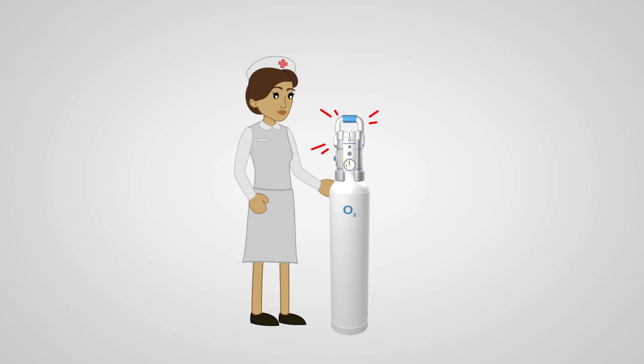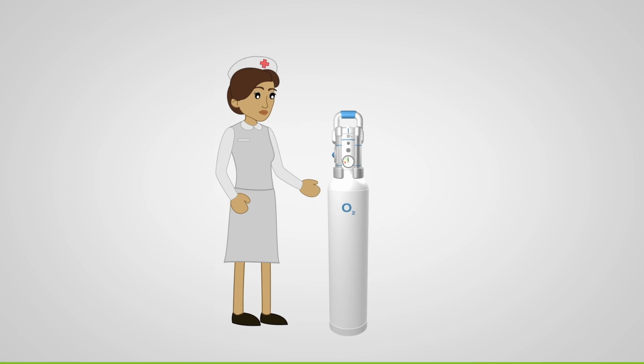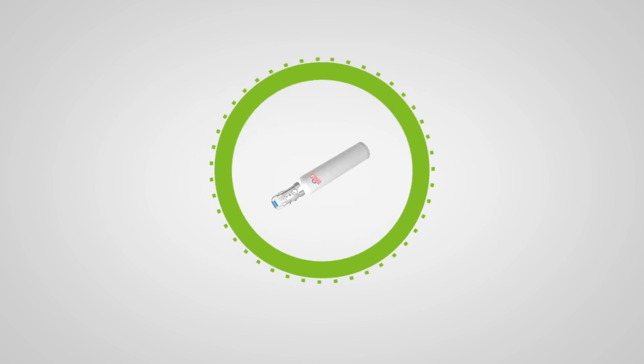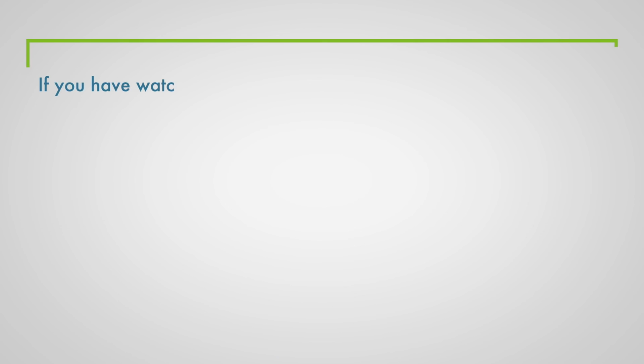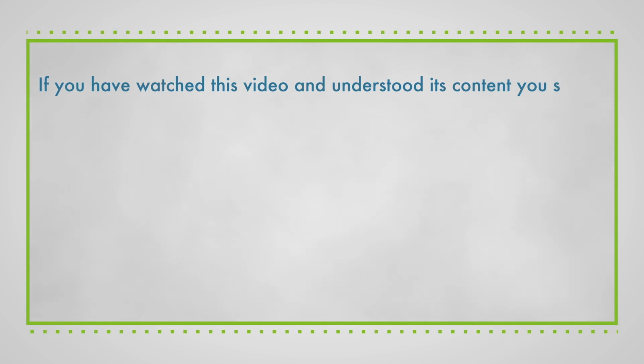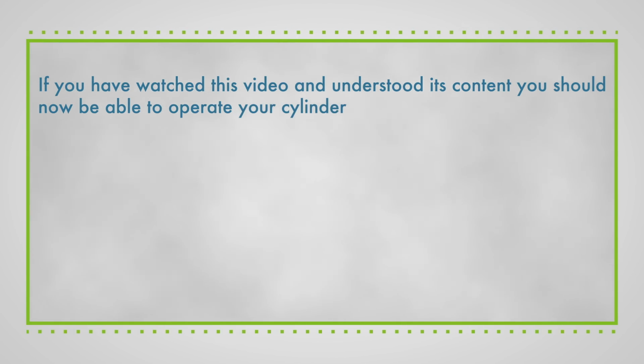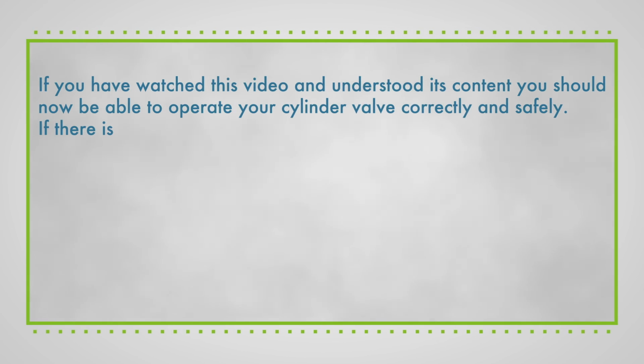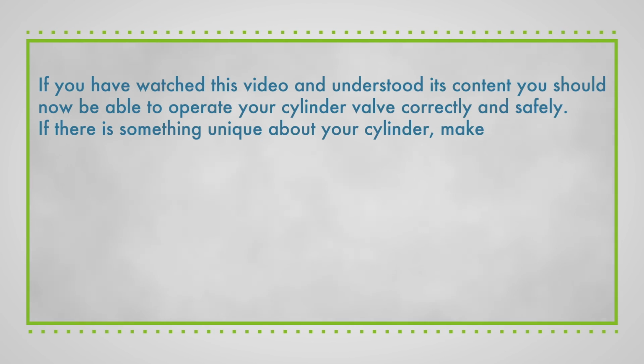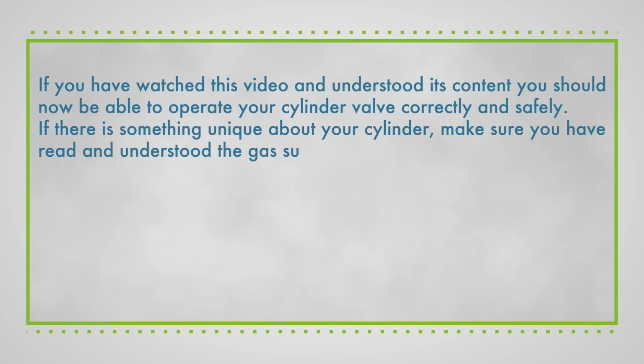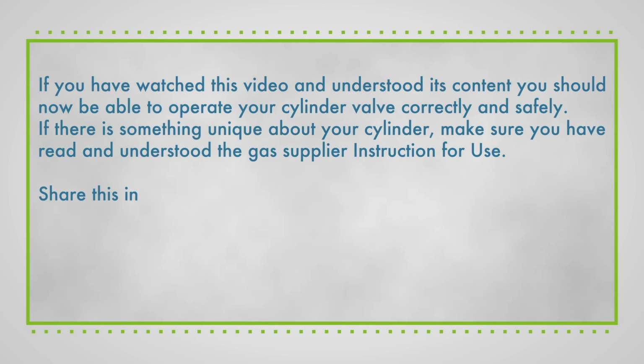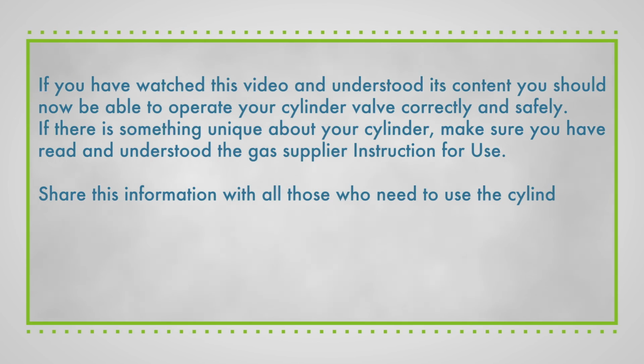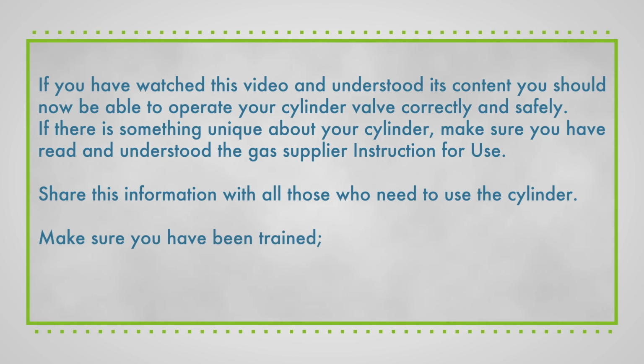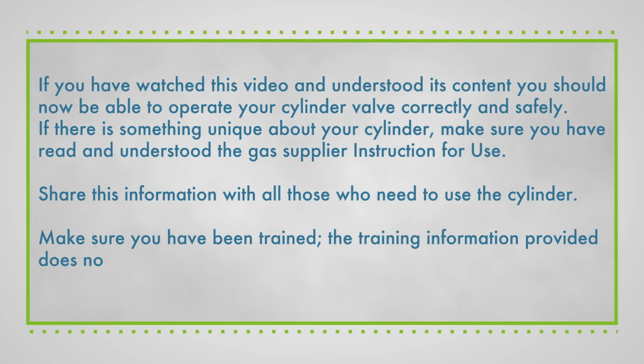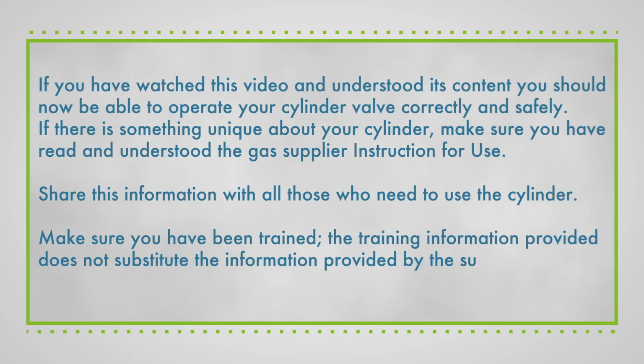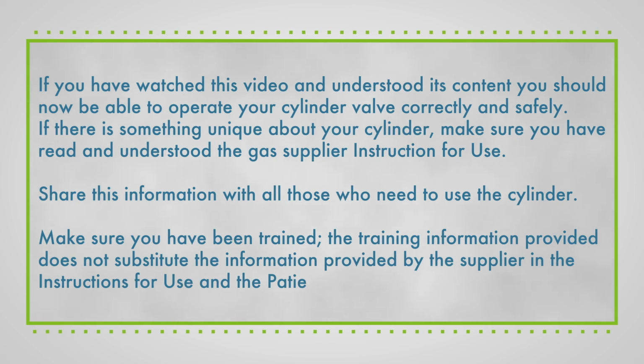If you noticed a malfunction of the valve during use, label the cylinder indicating the fault and inform the gas supplier. If you have watched this video and understood its content, you should now be able to operate your cylinder valve correctly and safely. If there is something unique about your cylinder, make sure you have read and understood the gas supplier instruction for use. Share this information with all those who need to use the cylinder. Make sure you have been trained. The training information provided does not substitute the information provided by the supplier in the instructions for use and the patient information leaflet.